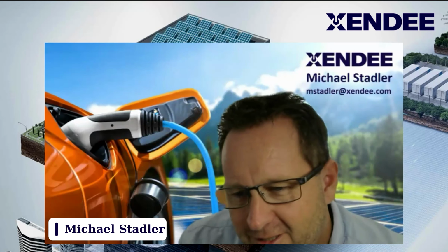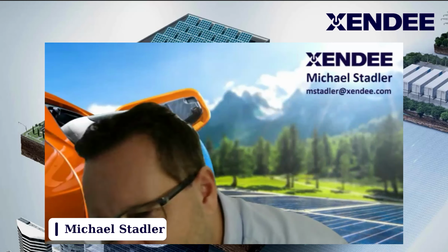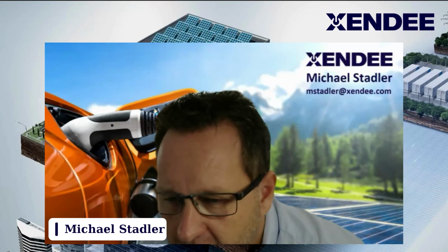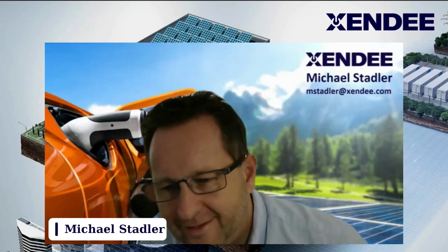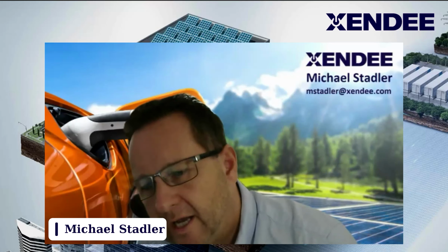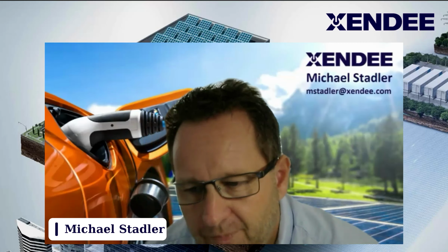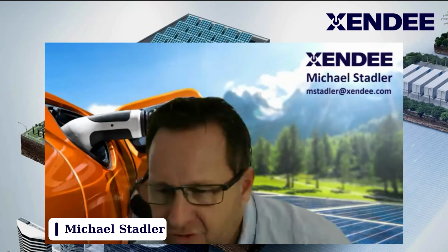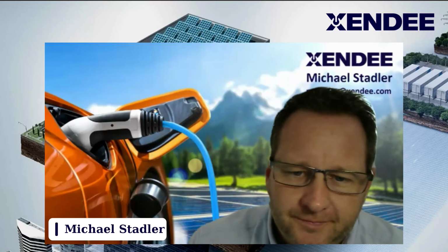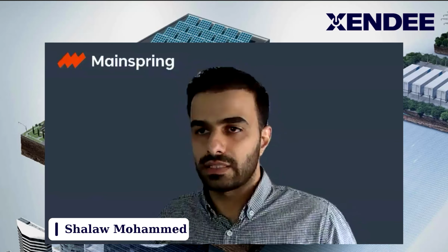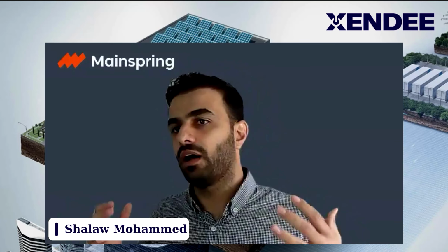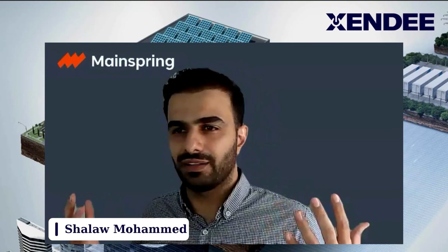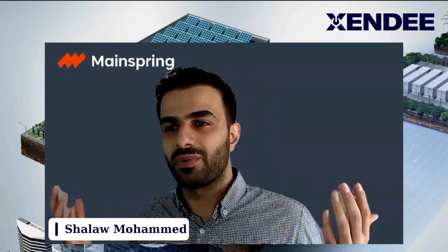Yep. I saw a couple of other Xendee questions. I will get back to this, but Ken is asking if there's any derating that you consider depending on the elevation and cold climates or hot climates. Is there also an impact of salt on the engine? So derates, yeah. We do account for altitude and temperature derates. That's just physics. You can't really get away from it.